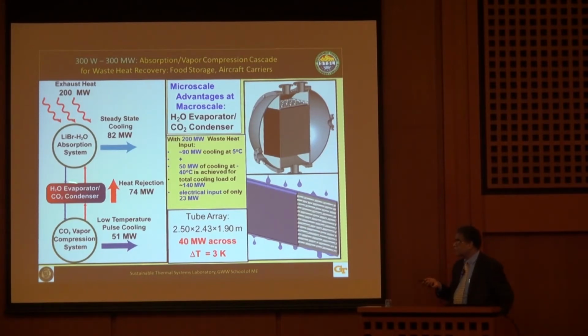But to make this happen, you need evaporation of water and condensation of CO2. CO2 is a very high pressure fluid, while water evaporation occurs at almost near vacuum conditions. This is a tricky problem, and the solution we came up with is to use microscale condensation of CO2 inside flat tubes, like automotive heat exchangers.